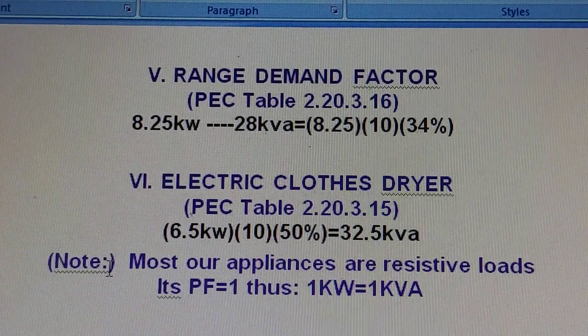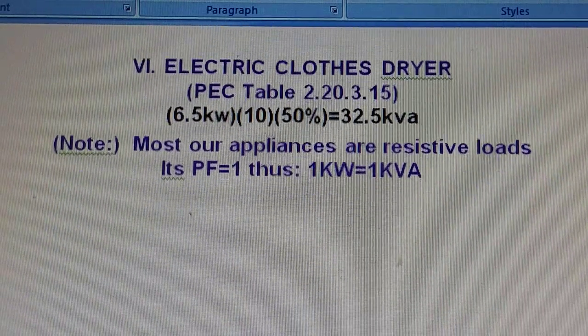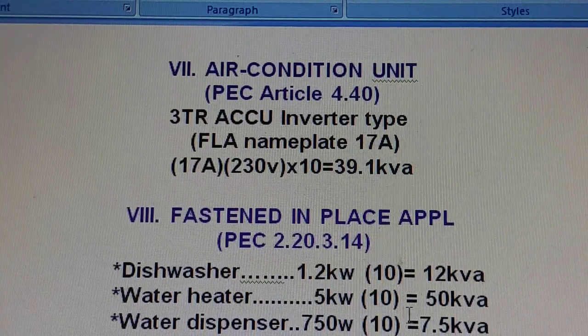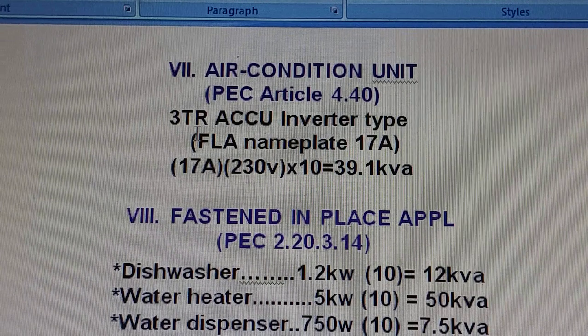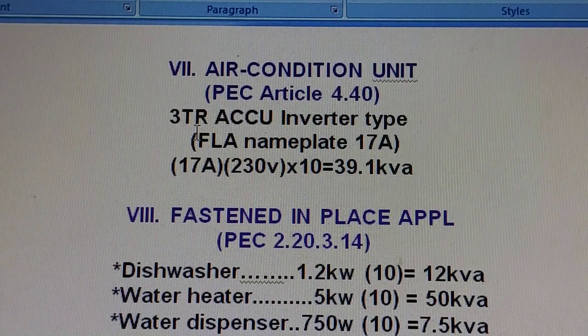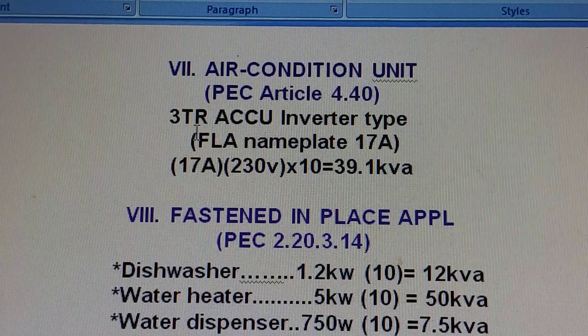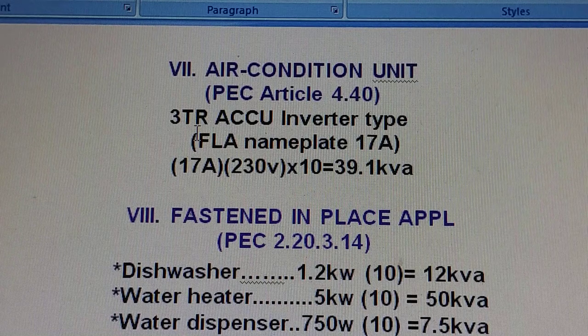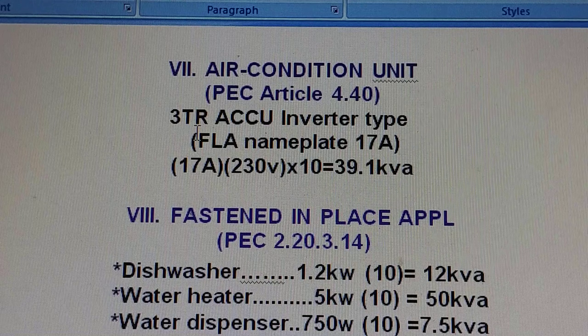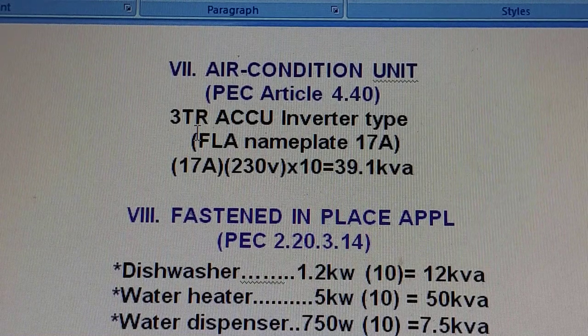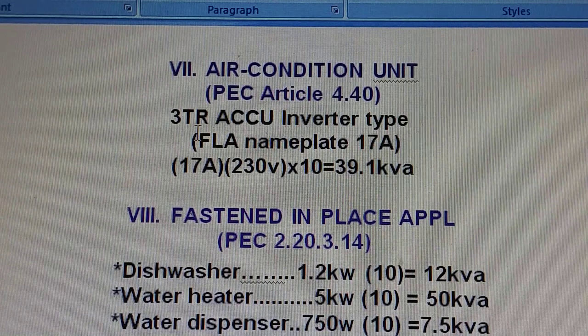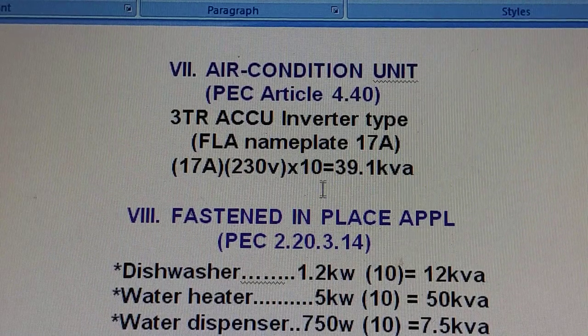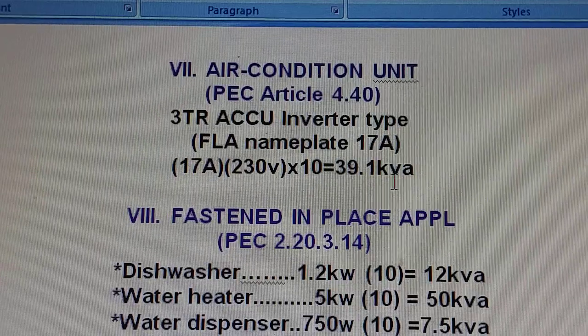For the air conditioning unit, we refer to Article 440. We are only getting the FLA from the nameplate of the air conditioning motor. For the 3-ton unit, we have 17 amps FLA — this is the standard for the 3-ton AC that I use in my design calculations for electrical plans. We multiply FLA times 230 volts times 10 condo units, giving us 39.1 kVA.